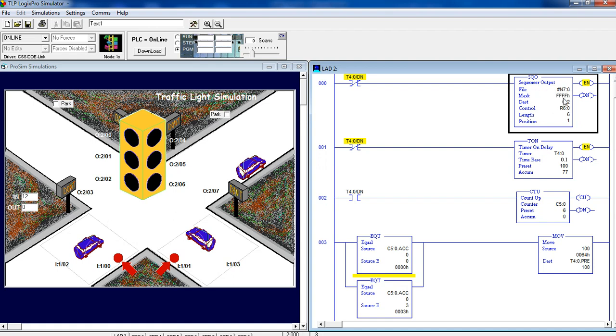I could have used just FF to pass only the first eight bits. The destination is O2:0, which is O2 — the output file where all the lights are controlled. Whatever is in N7:0 through N7:5 will be passed through to O2. Because the length is six, it cycles through N7:1, 2, 3, 4, 5, and 6, then goes back to N7:1.